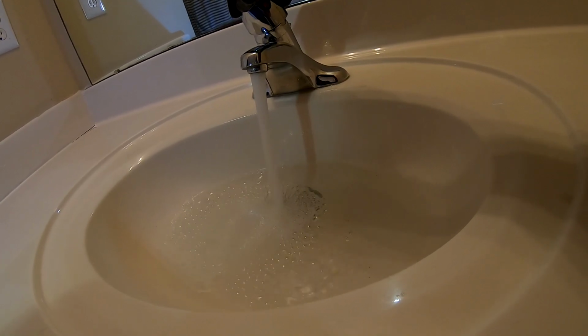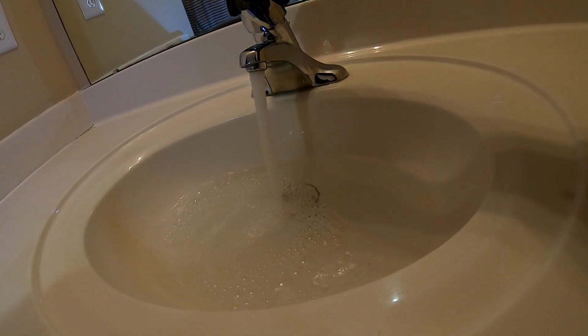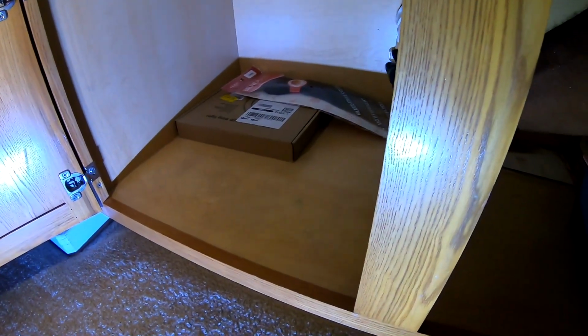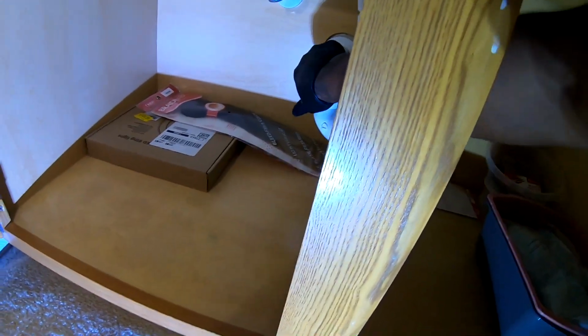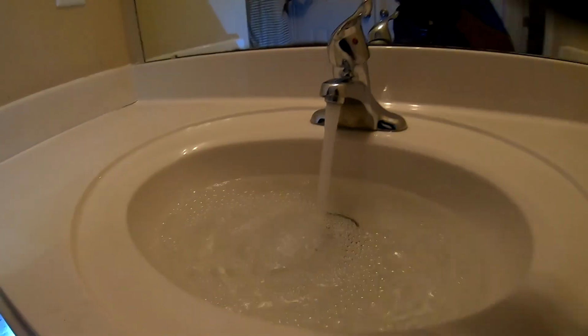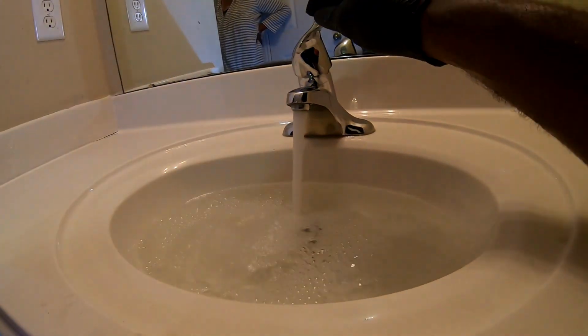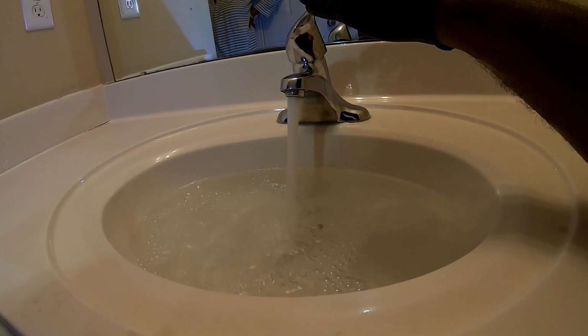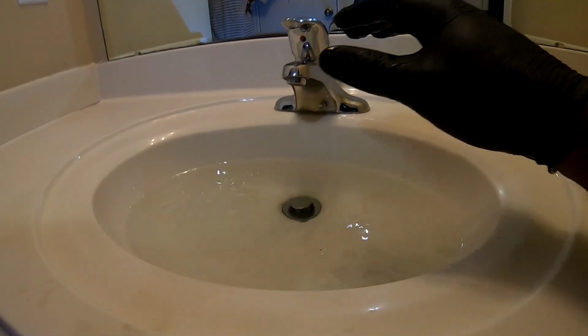I'm telling you, they have the problem. Yeah, you can pour some in there if you want to. I would like to take it loose, but I can't do it. A plumber will have to do it and put a snake in there and get it unclogged real good. But if it's draining, especially since you're not using it that much, but if it gets stopped up, it's going to cause my AC drain to not be able to drain. In other words, we got to make sure this right here stays clear. So maybe every now and then, because that's the thing.